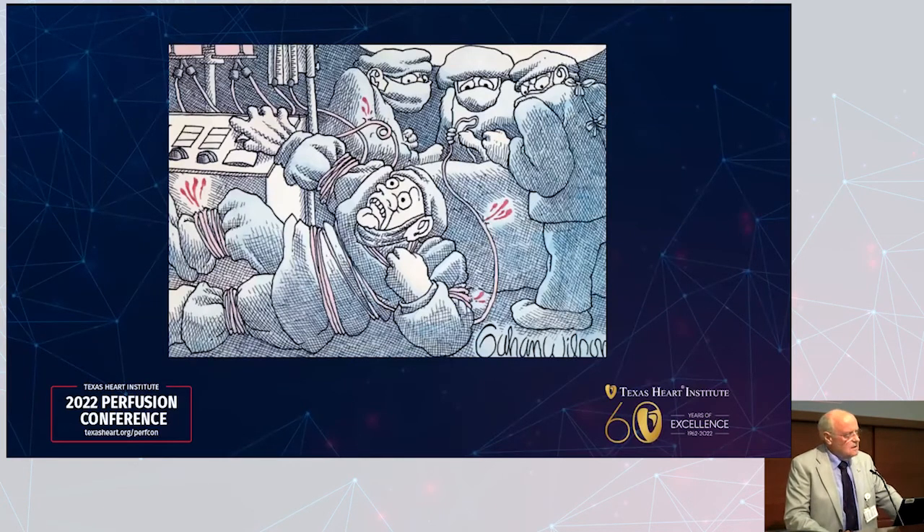Monitoring devices were comprehensive — they measured everything in cardiopulmonary bypass. This included pre- and post-pressure sites of hemoconcentrators, membrane oxygenators, arterial filters, water temperature sites, other blood sites, high and low blood levels, blood and water flows, blood gases, coagulation, and more. The results from these studies led to changes in their perfusion practices.